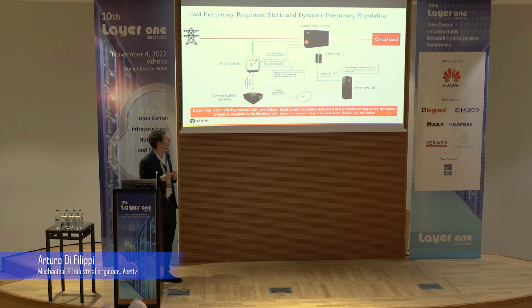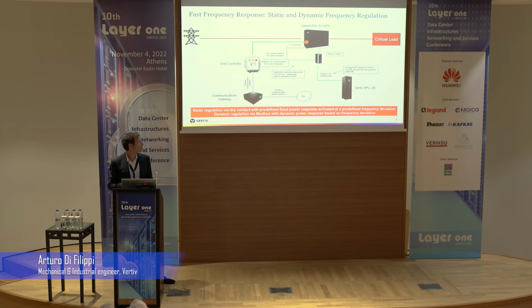One is static frequency regulation, done through a dry contact connection between the UPS and the controller. The other is dynamic frequency regulation, done through a Modbus connection. The difference is that with static regulation you have a fixed response from the UPS to grid frequency variations, while with dynamic regulation you have continuous verification of the status of the grid.